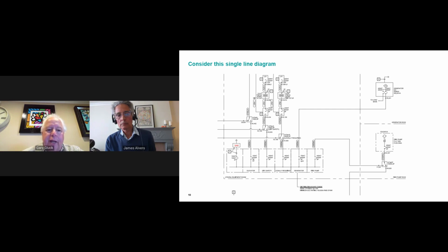So let's look at a single line diagram that illustrates a typical generator distribution switchboard. Now, this particular single line came across my desk with the question that typically accompanies just about everything that comes across my desk, which is how do we optimize this board? Because if we go by what's been drawn, this board is 6 sections, and if we figure that on average it varies among manufacturers, let's say somewhere in the vicinity of 3 feet, I mean, the switchboard could be 18 feet wide. So the question comes to me, what can we do with it?